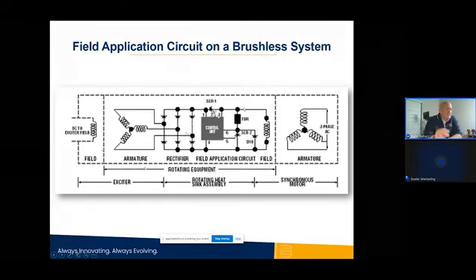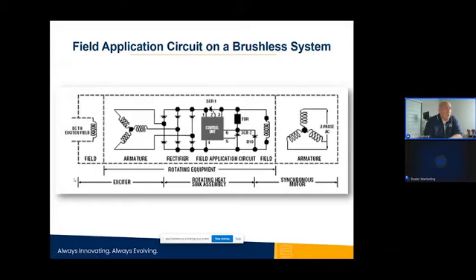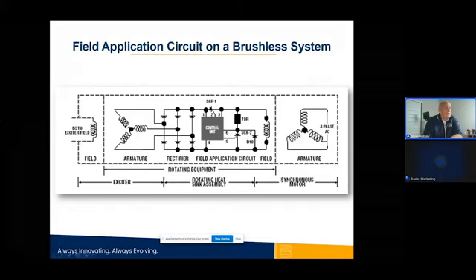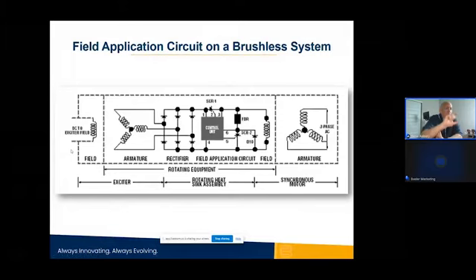So all of this is done pretty quick. You've got your motor starting time that you want to set your protection, and set the controller out here that's exciting the field. You want that set so that once that field is applied, the controller will go from a manual mode of regulation, or running in what we call FCR mode, field current regulator. We would have that set to the full load capability of the motor itself.